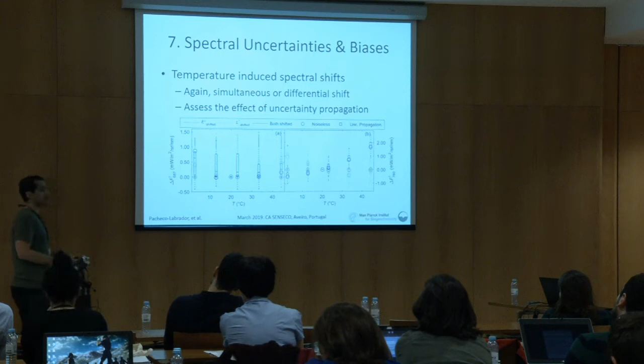And this is very tricky because characterizing nonlinearity, traditionally for remote sensing or proximal sensing applications, we always look at the top of the spectral range, because usually that is where we find the biggest changes, and also because at the bottom there is a lot of noise. And okay, we assume that we are not going to measure them because we are going to optimize, and that's good. But when we measure fluorescence, we have deep absorption lines, and you have very different signals inside and outside the oxygen bands or the Fraunhofer lines where we actually want to retrieve fluorescence.